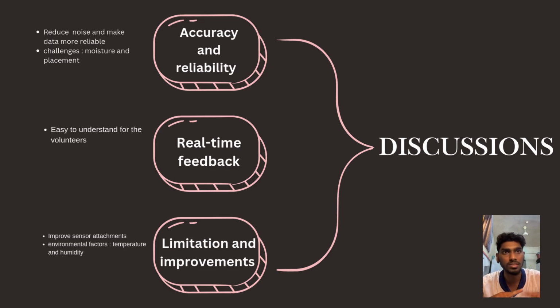One of the challenges we faced during testing was placing the sensor on the fingertip. If the sensor is placed on the knuckle of the finger, it won't show an accurate reading, so it's better to place the sensor on the fingertip.